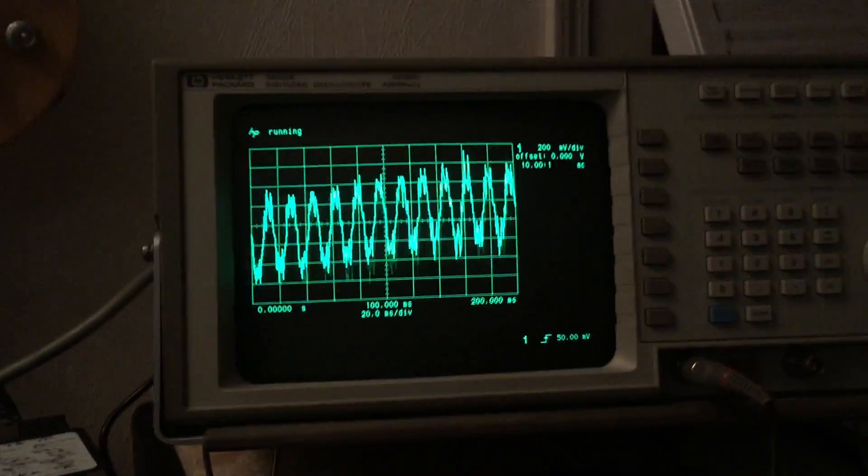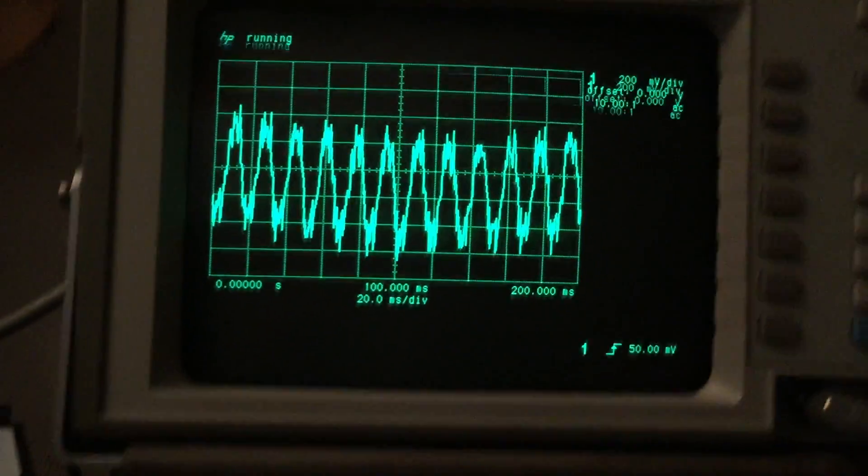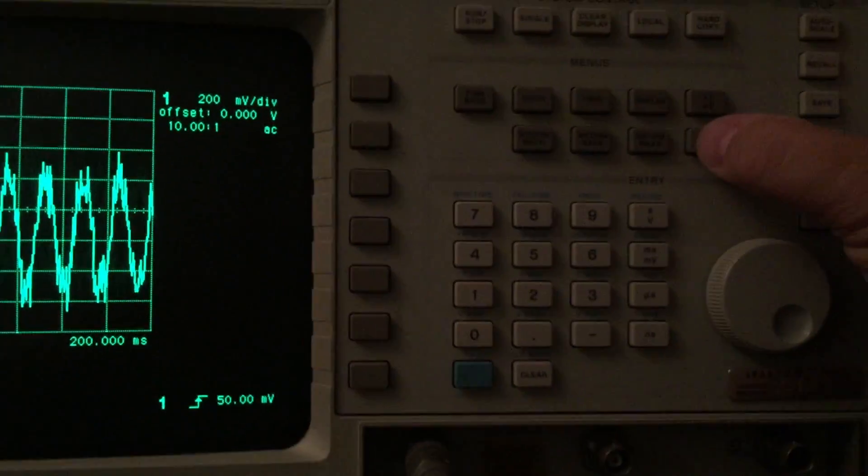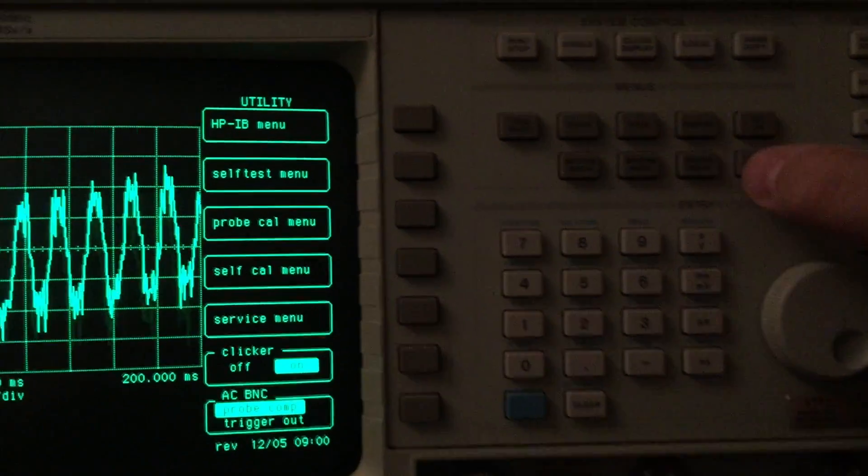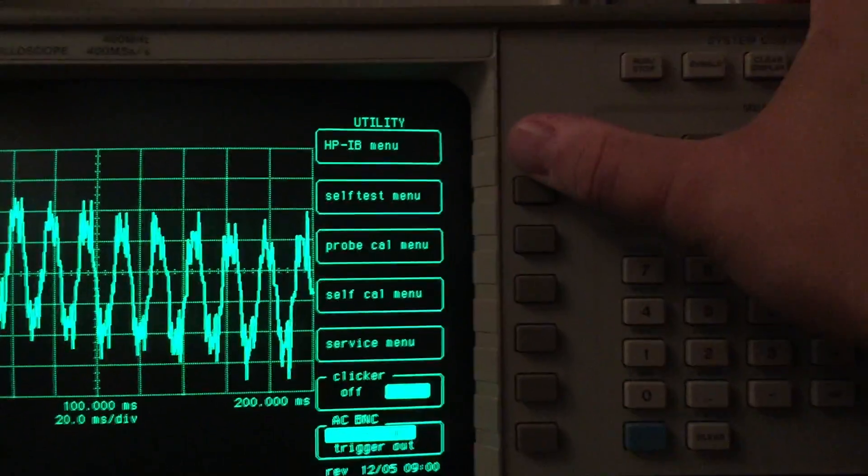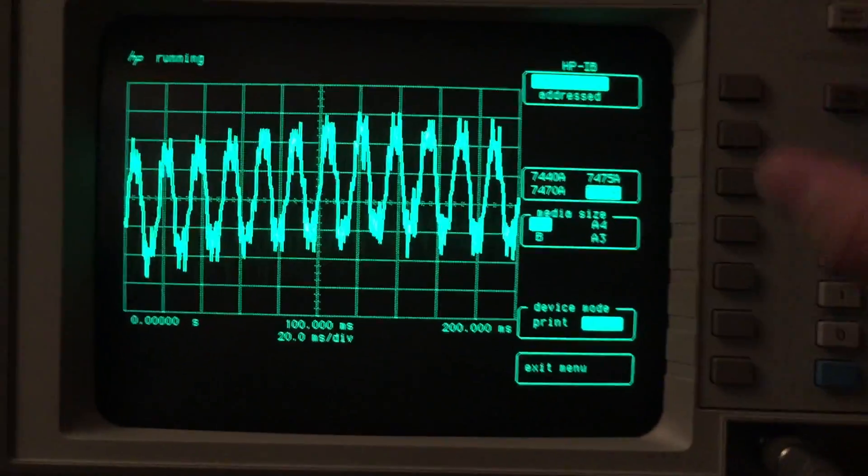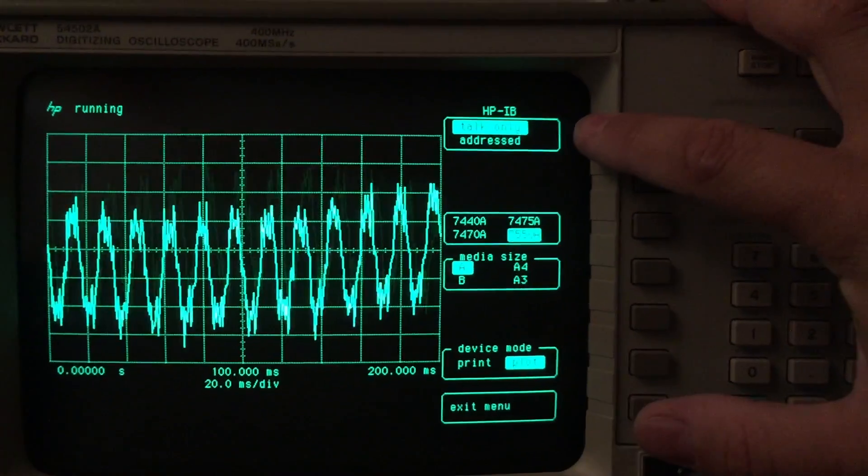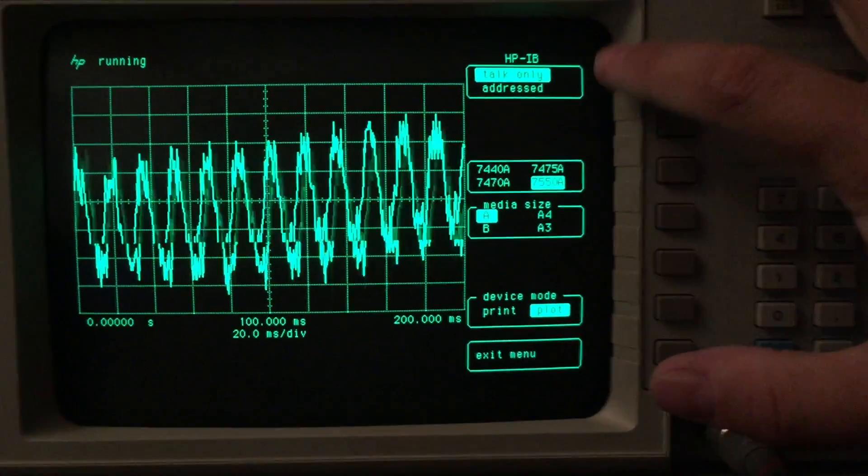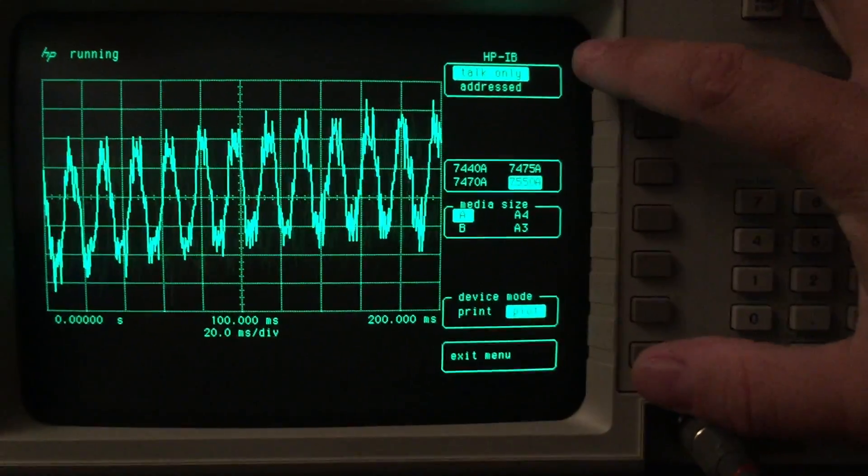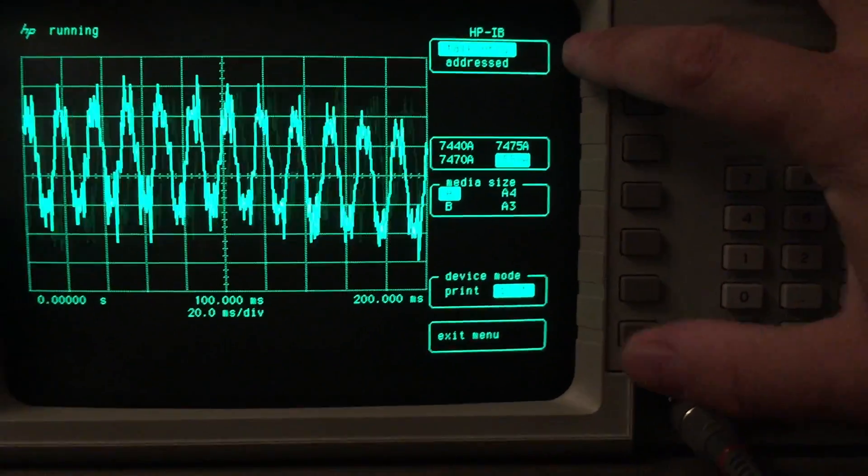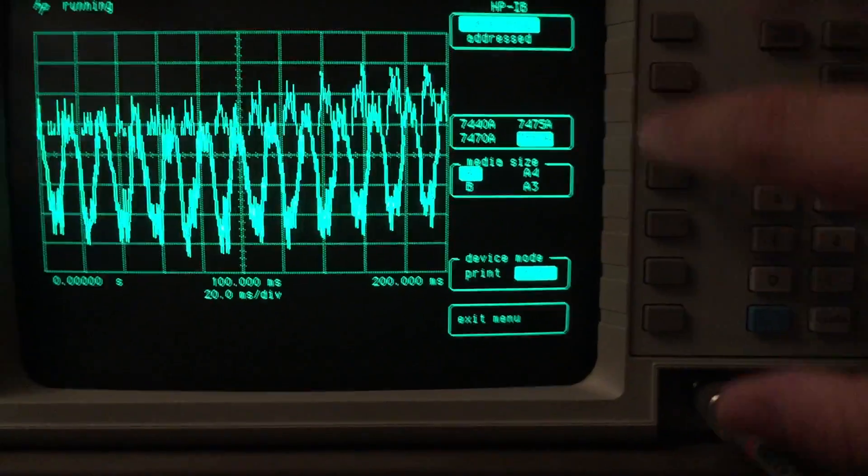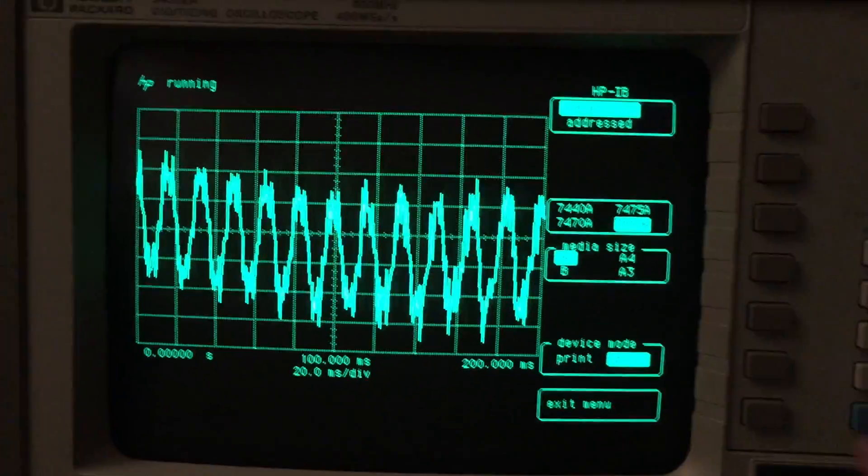What you do is on this oscilloscope, go into utilities and then the HP-IB menu. There's two selections - it says talk only and addressed. The only way to get this to plot is you have to use talk only, and then you select the plotter you're using, your media size, and then plot. So talk only, and then you turn this back to show the waveform.